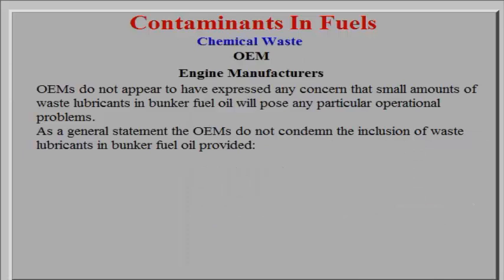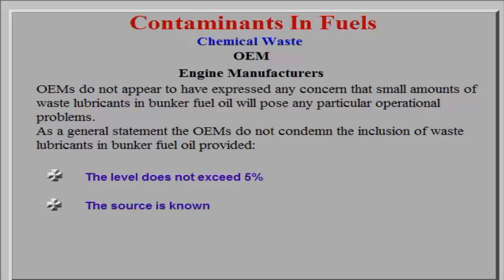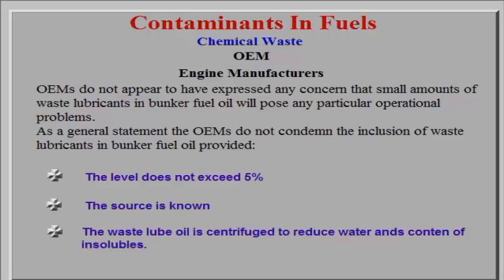As a general statement, the engine manufacturers do not condemn the inclusion of waste lubricants in bunker fuel oil, provided the level does not exceed 5%, the source is known, and the waste lube oil is centrifuged to reduce water content and insolubles.